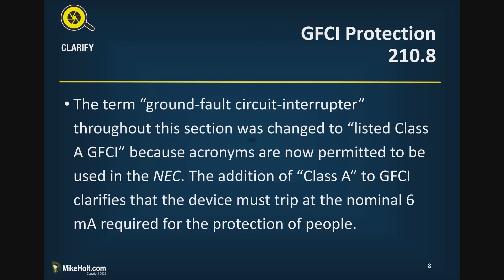We were just talking about acronyms, but look what it says: the term 'ground fault circuit interrupter' throughout the section was changed to 'a listed class A GFCI' because acronyms are now permitted to be used in the code. The addition of 'class A' to GFCI clarifies the device must trip at the nominal six milliampere or larger for the protection of people.